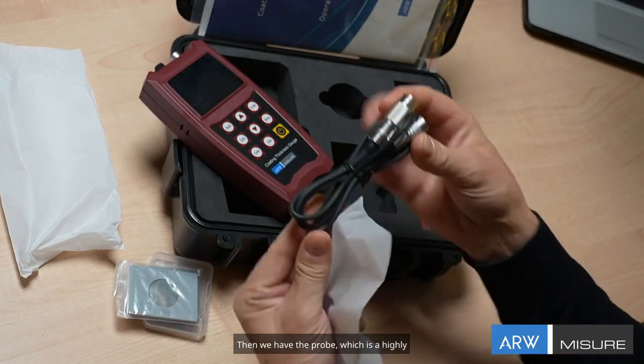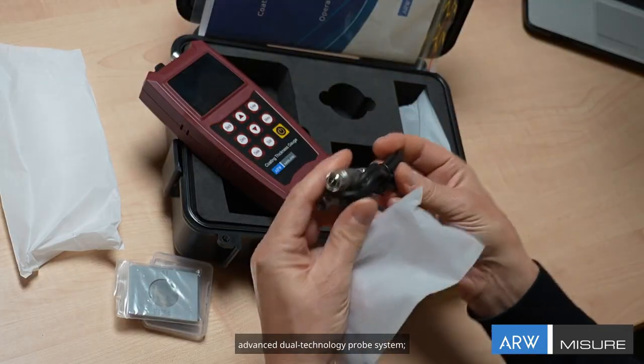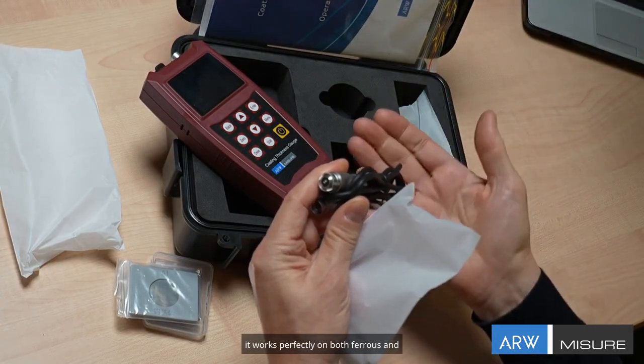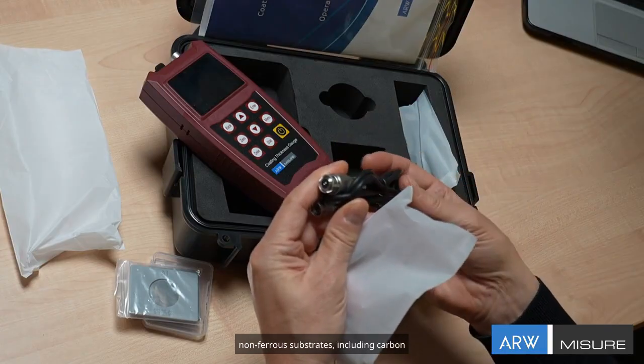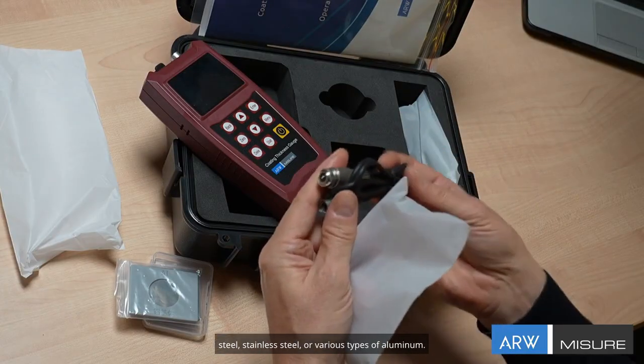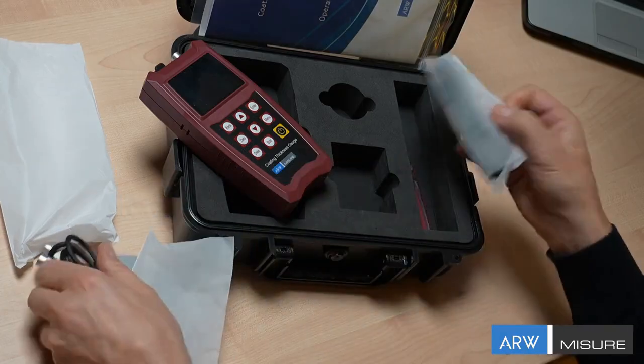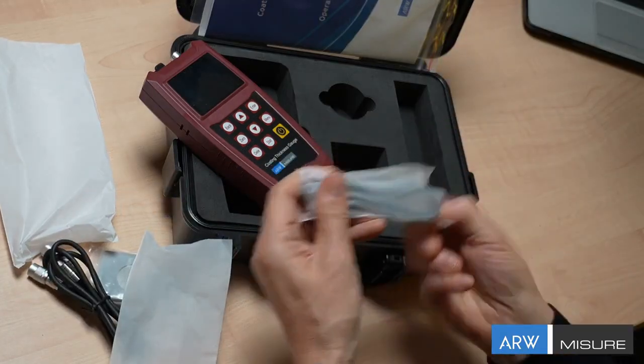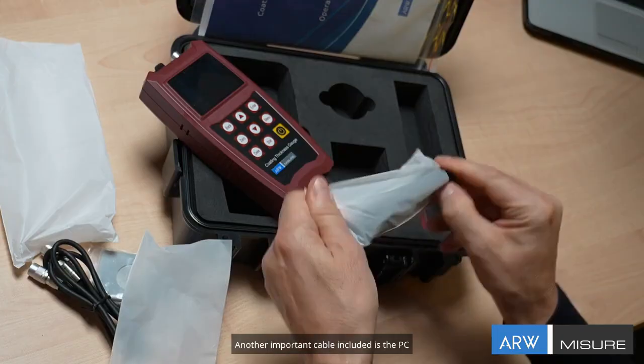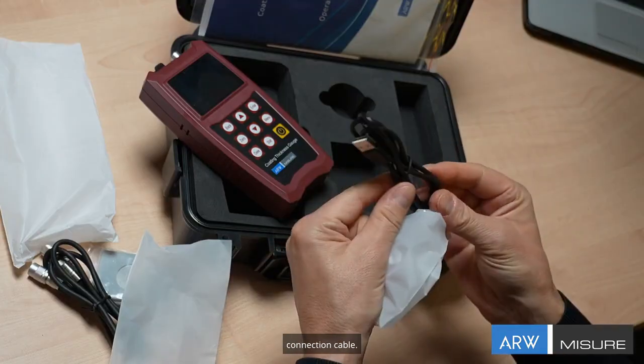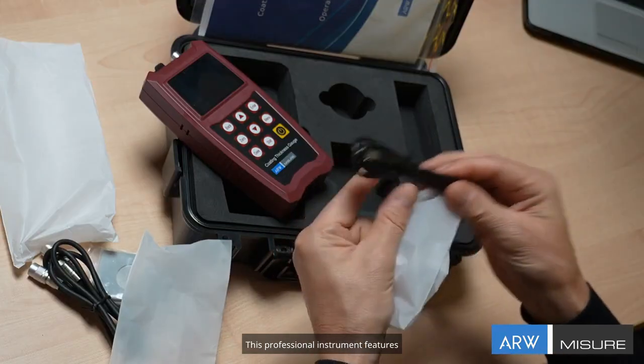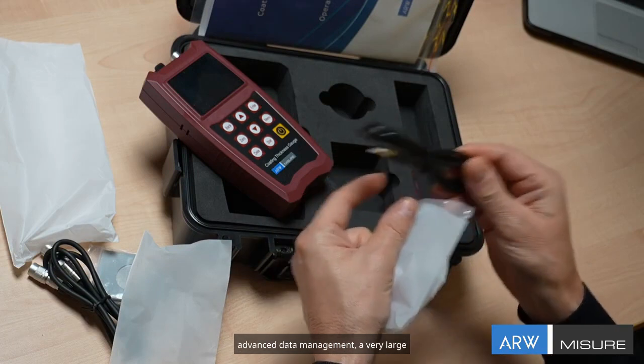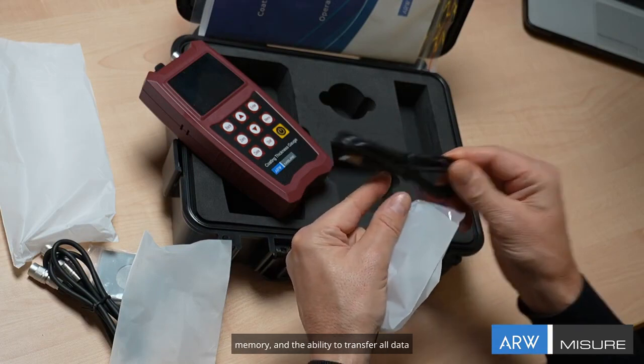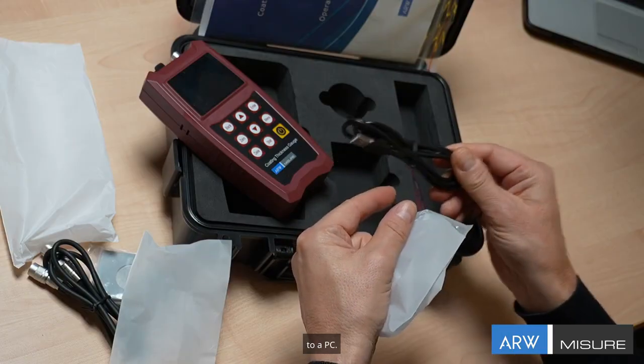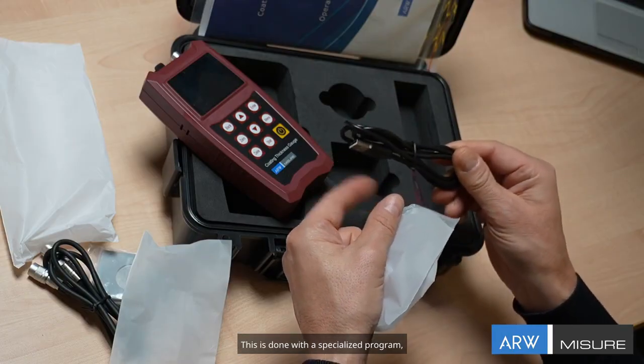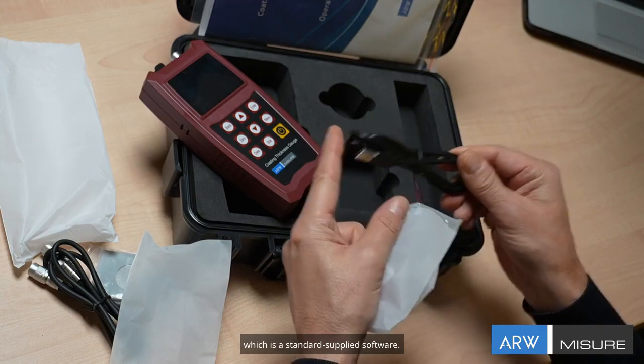Then we have the probe, which is a highly advanced dual technology probe system. It works perfectly on both ferrous and non-ferrous substrates, including carbon steel, stainless steel, or various types of aluminum. Another important cable included is the PC connection cable. This professional instrument features advanced data management, a very large memory, and the ability to transfer all data to a PC. This is done with a specialized program, which is a standard supplied software.